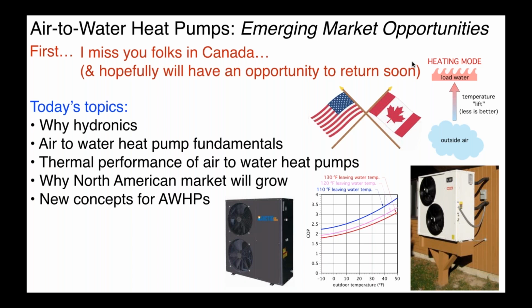So with that, let's talk about today's topics. I always like to start any session that involves hydronics with fundamentals. Why do we choose to go to water-based delivery with a heat pump instead of, let's say, air-based delivery? What's the advantage there? And then we're going to get right into the fundamentals of what an air-to-water heat pump is for those of you that have never worked with these systems before. If you're familiar at all with basic refrigeration and basic heat pump operation, you'll see these are not that different from other types of heat pumps.